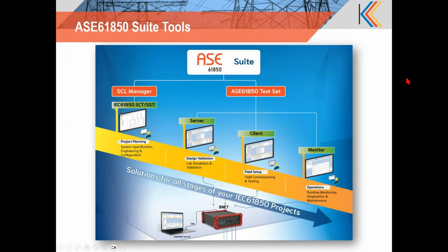Okay, coming to the ASE61850 suite of products, under this brand we have SCL Manager. It's a full-fledged IEC61850 SCT. It can do substation configuration and substation specification. So you can use this in the project planning phase by importing all the ICD files, CID files, and create the full engineering of the substation.